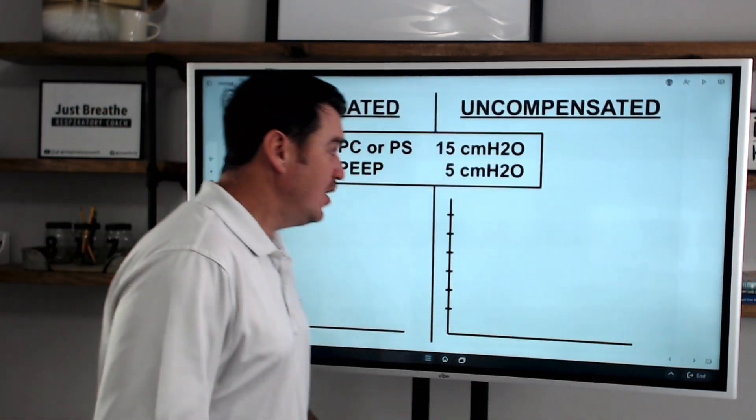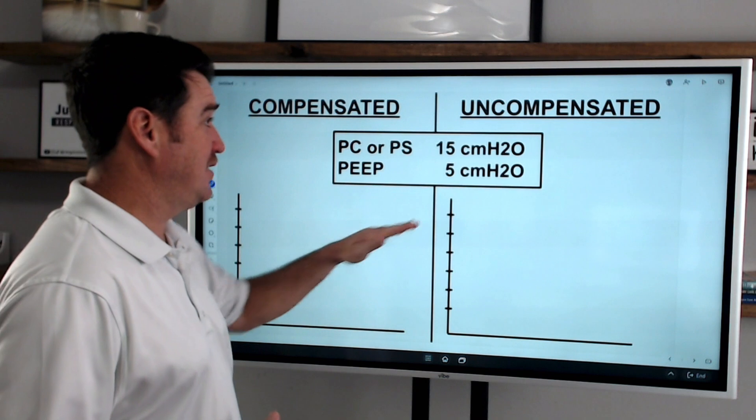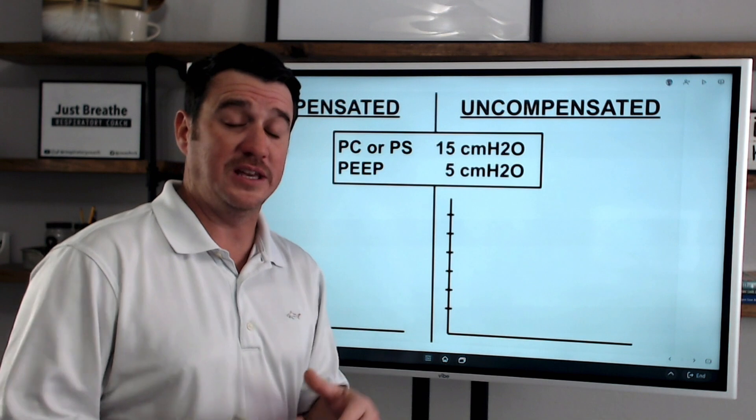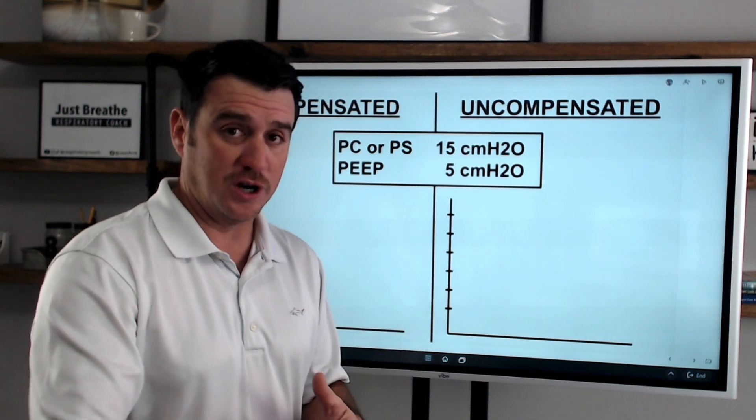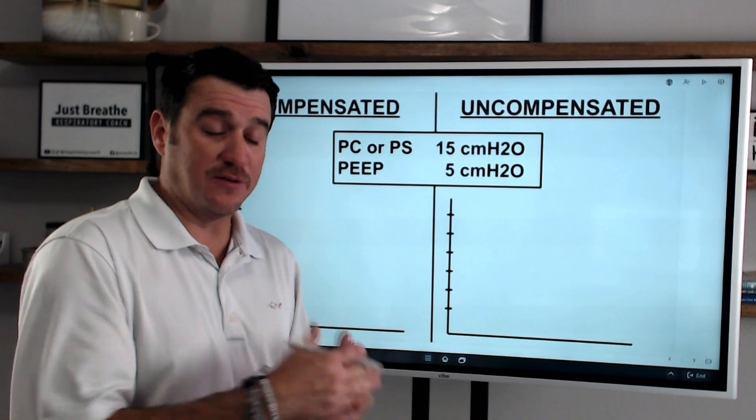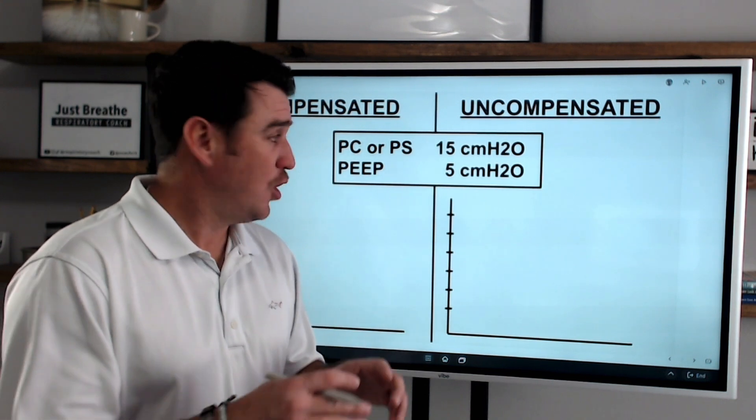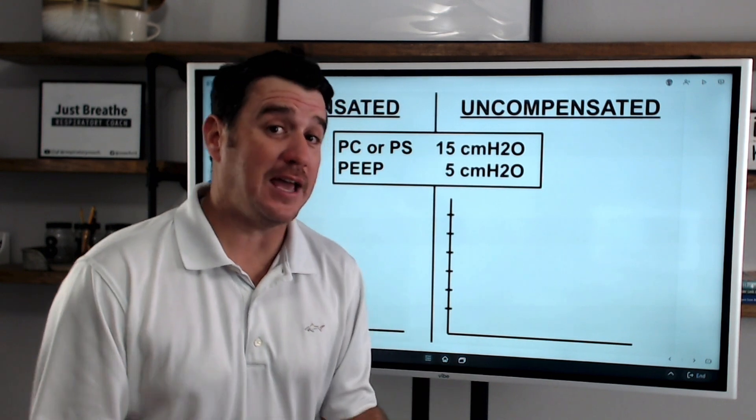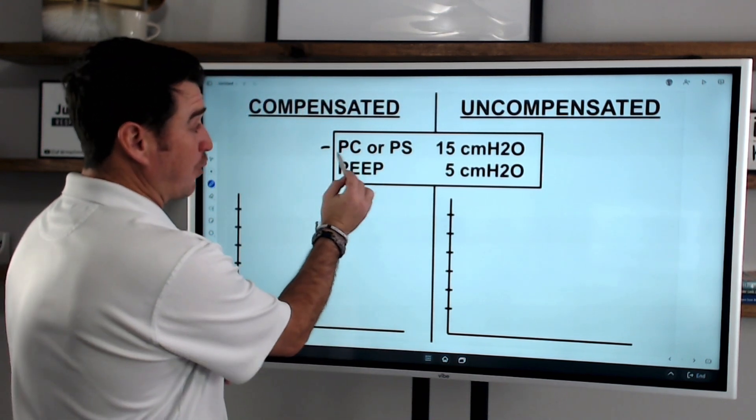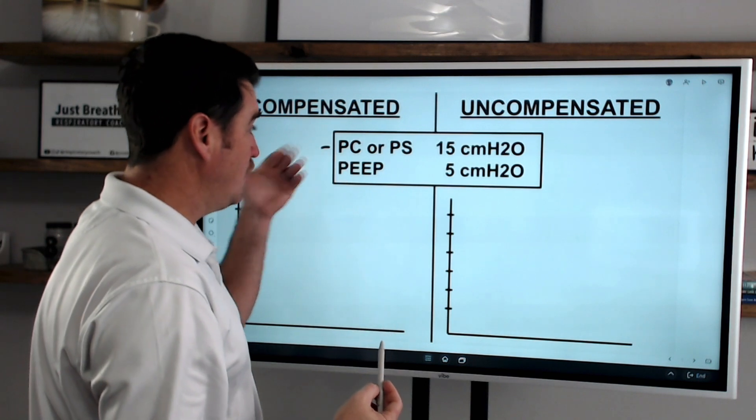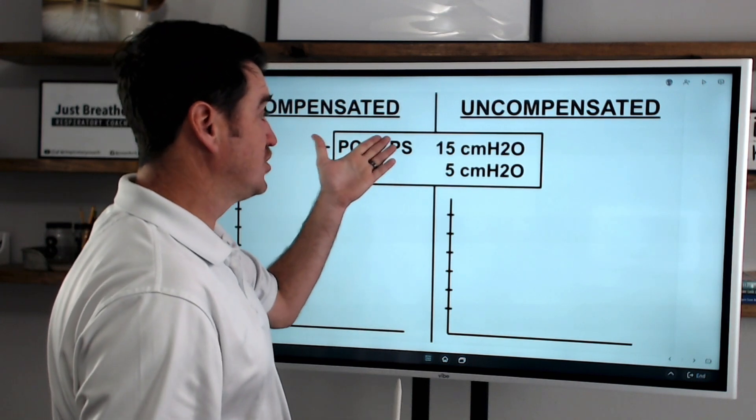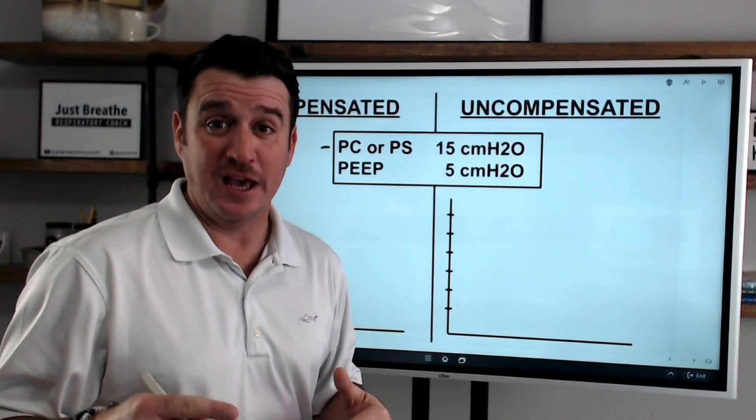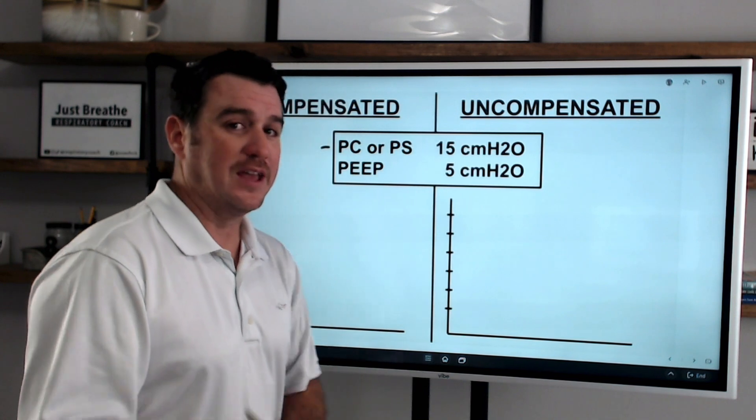Now, when you look at compensated versus uncompensated, what we're talking about is anytime we are going to be applying pressure onto a baseline, the ventilator needs to understand where it is going to stop at. So, for example, anytime we're going to dial in either a pressure control setting or if we're going to dial in a pressure support setting, then PEEP compensated versus uncompensated becomes very important. Let me show you why.